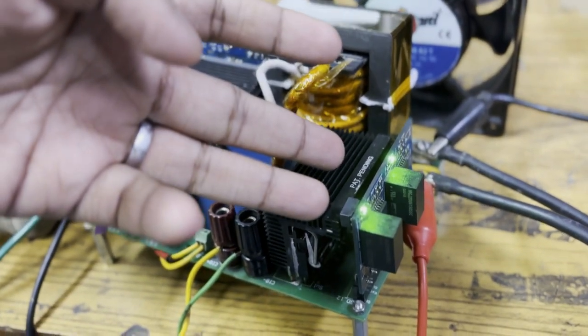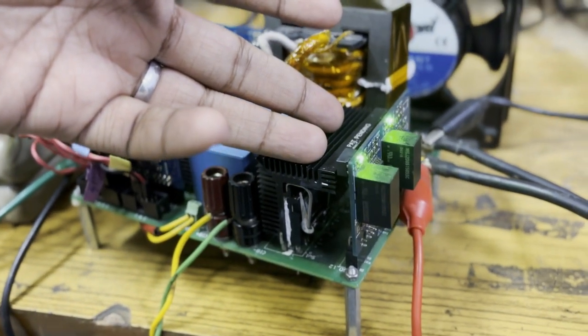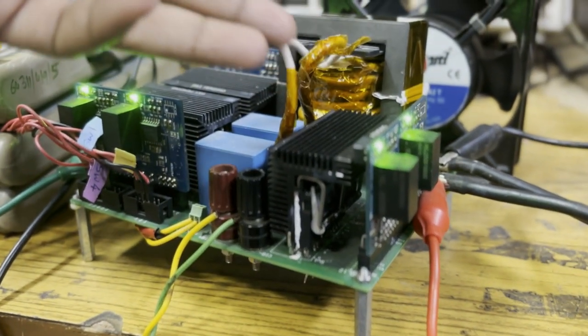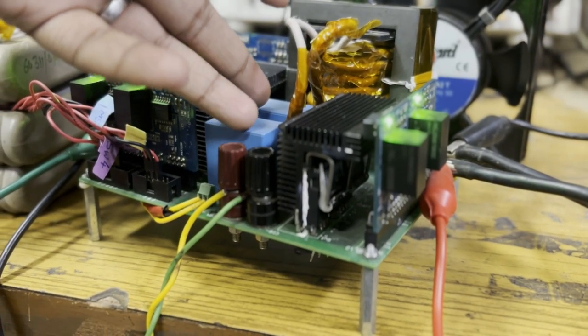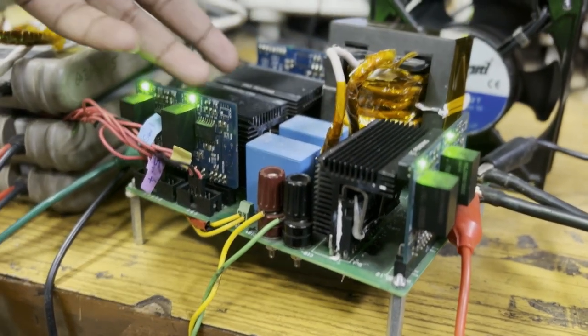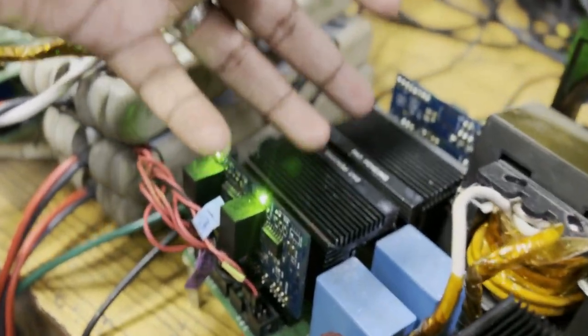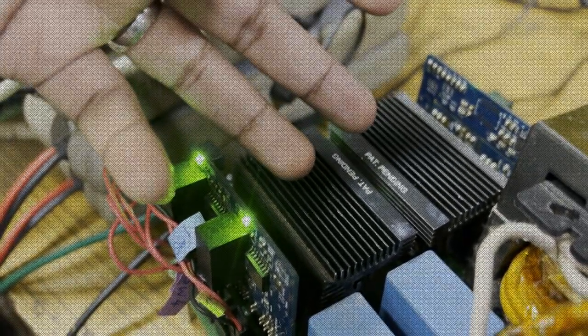Traditionally, an unfolder inverter has two stages. In the front end, a high frequency DC-DC stage takes a stiff DC input and creates a pulsating DC akin to a DBR output at the intermediate DC bus. Then a full bridge inverter stage creates a pure sine wave by switching at line frequency.